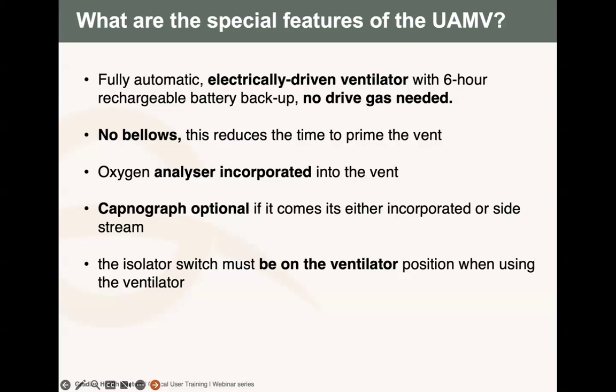And then that surgery might take maximum maybe 2, 3.5 or 4 hours. So you'll be safe. You can still run your anesthesia using your mechanical ventilation with the UAMV. And another thing that we need to emphasize is that the type of ventilation, or the type of machine or ventilator that we have on the UAMV, is electrically driven. It doesn't need pressure like many other ventilators, which are pressure driven, okay?